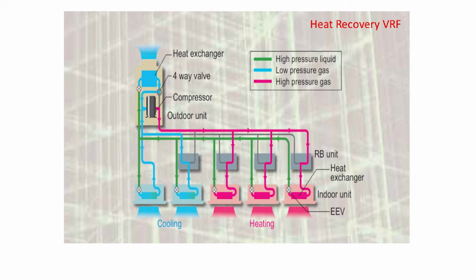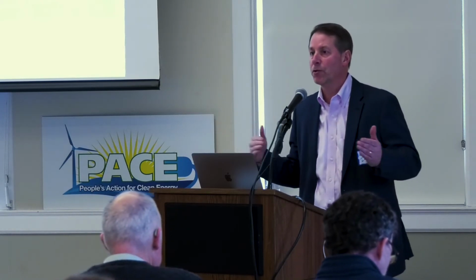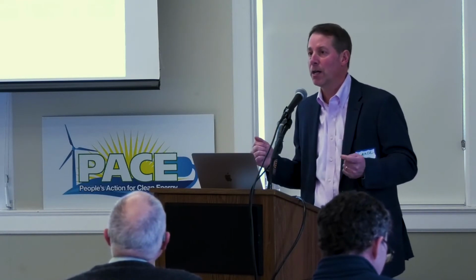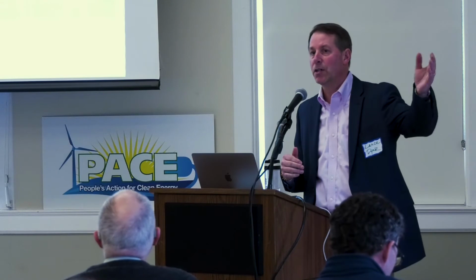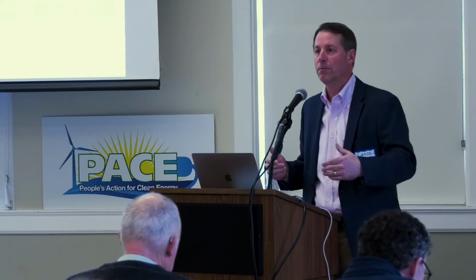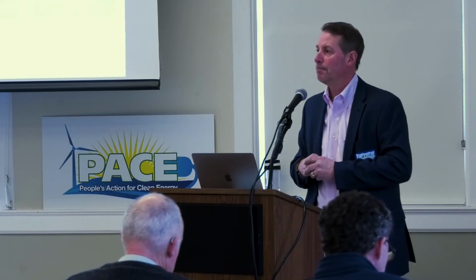What's nice about this type of system is if you take an example of a building that has some east-facing glass, let's say, a line of classrooms, and maybe on the other side you have a center hallway, and the other side you have classrooms facing west. Well, you're going to have different temperature gradients based upon what type of day or what time of day it is. So the sun could be coming up in the east, and all of a sudden you're getting a solar gain. It could be 40 degrees outside, and you have a solar gain that's heating up. You have people, you have children, and you have a solar gain, whereas the other side of the building is not seeing that solar gain, and therefore they may need to be in a heating mode.